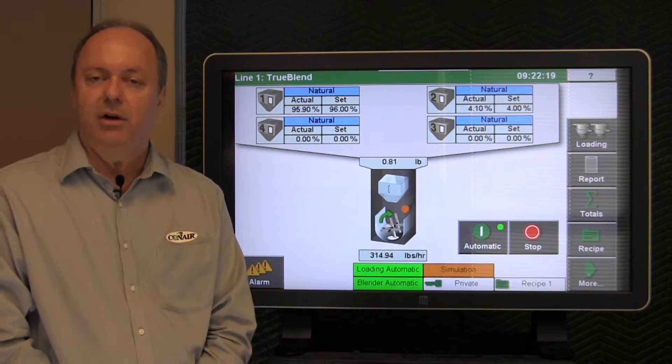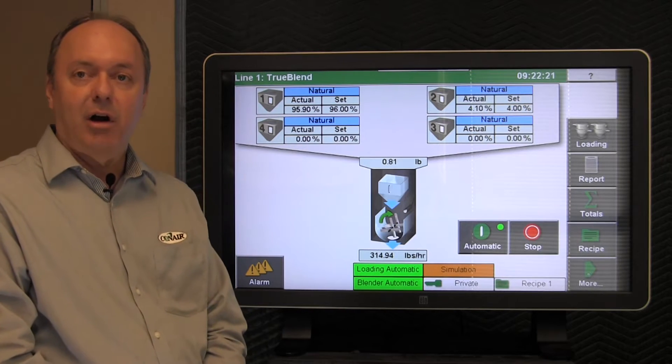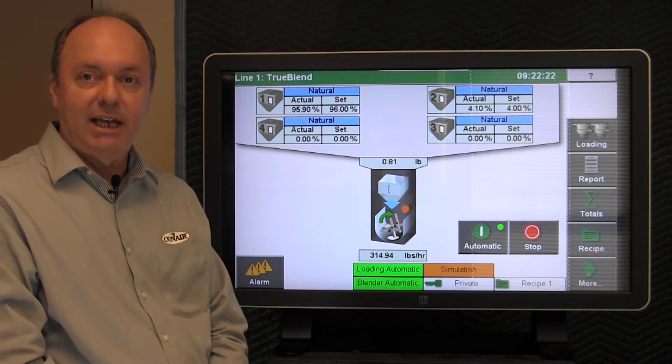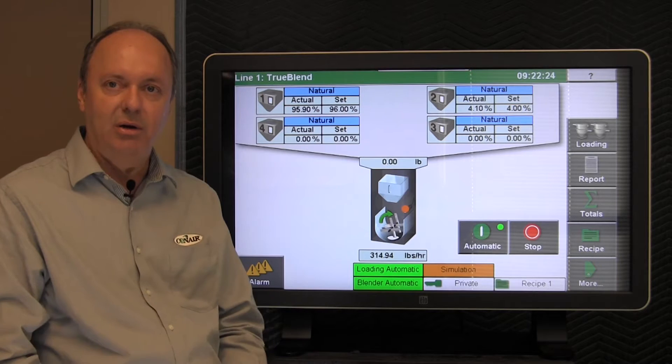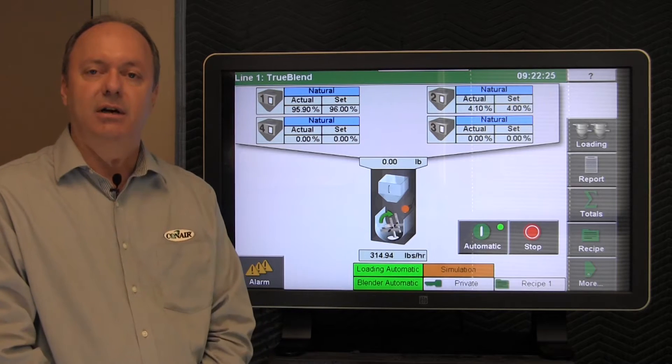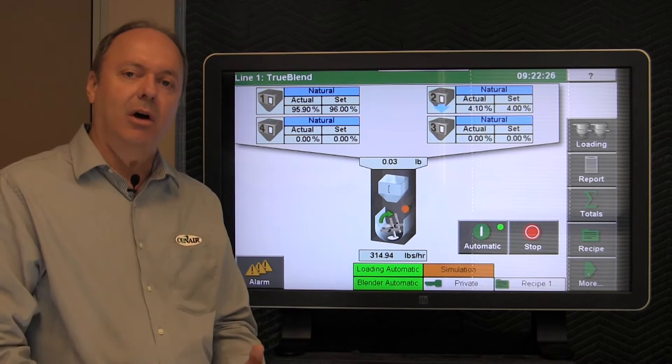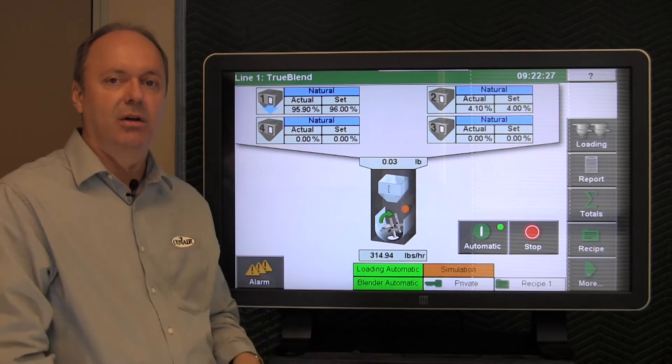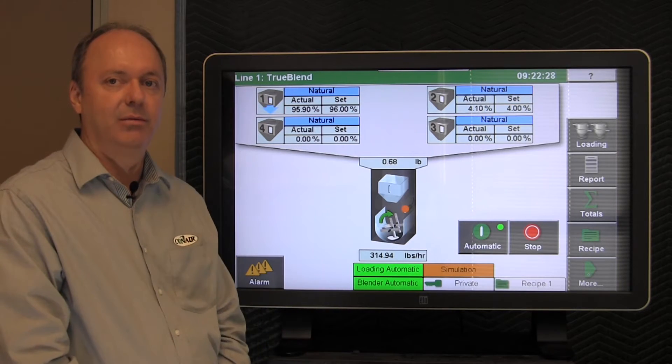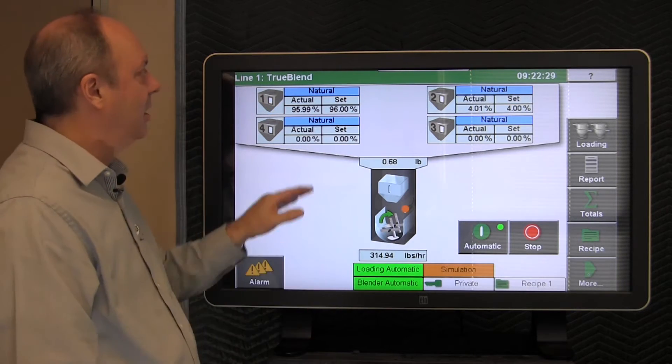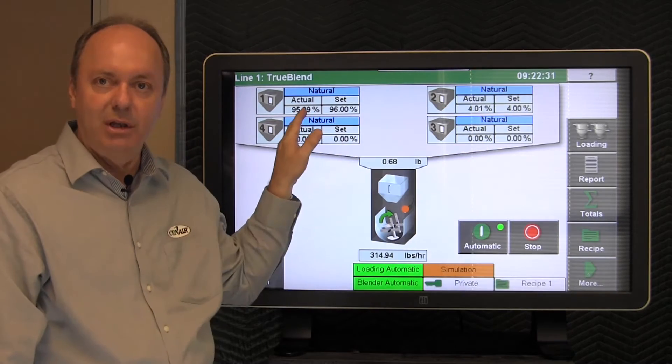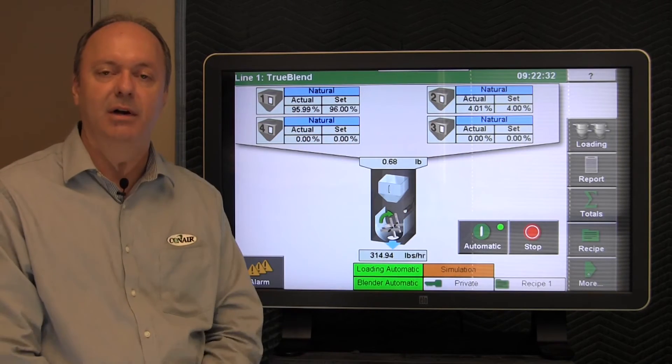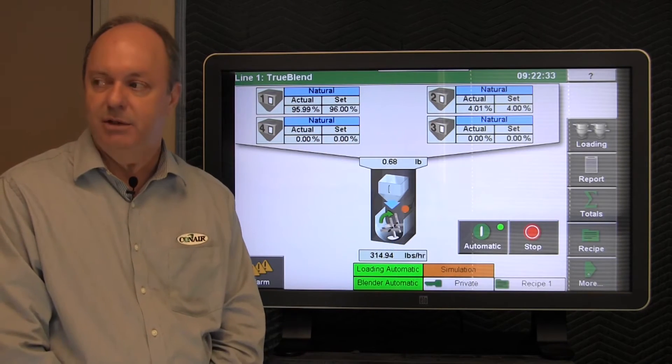You could also get a gate valve failure alarm which indicates that the gate is sticking, open or closed. So there's any number of alarms that might occur that would follow with these sets and actuals not actually lining up the way you'd like them to.